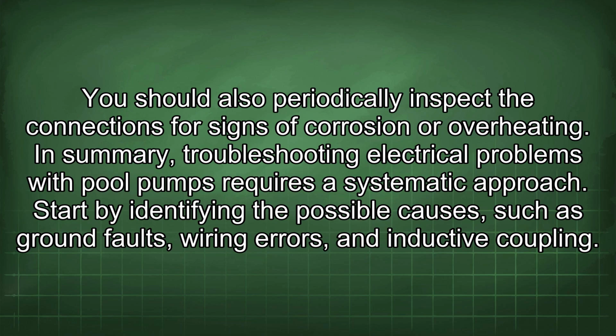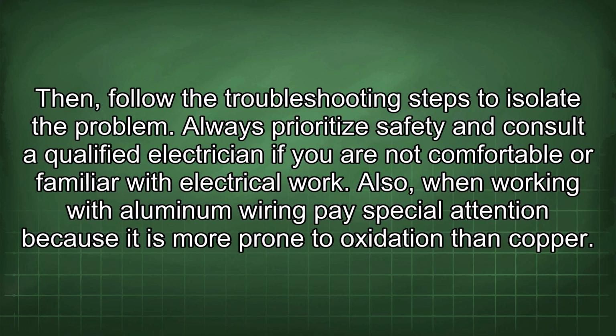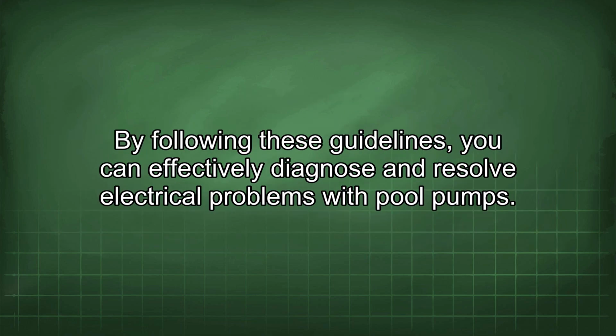In summary, troubleshooting electrical problems with pool pumps requires a systematic approach. Start by identifying the possible causes, such as ground faults, wiring errors, and inductive coupling. Then follow the troubleshooting steps to isolate the problem. Always prioritize safety and consult a qualified electrician if you are not comfortable or familiar with electrical work. Also, when working with aluminum wiring, pay special attention because it is more prone to oxidation than copper. By following these guidelines, you can effectively diagnose and resolve electrical problems with pool pumps.